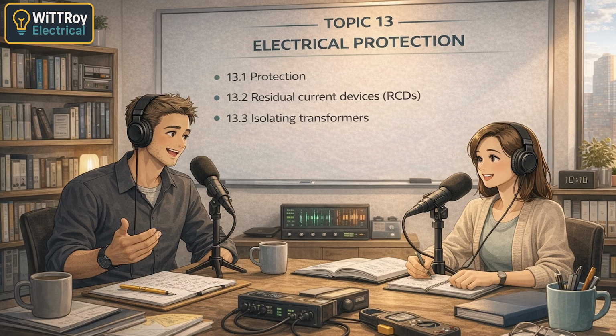So if it trips too slow or too fast, it's unsafe. Exactly. If any of those limits aren't met, the RCD is electrically unsafe. And it must be replaced. Yes, not repaired. Okay. Now let's move to 10 milliamp RCDs.